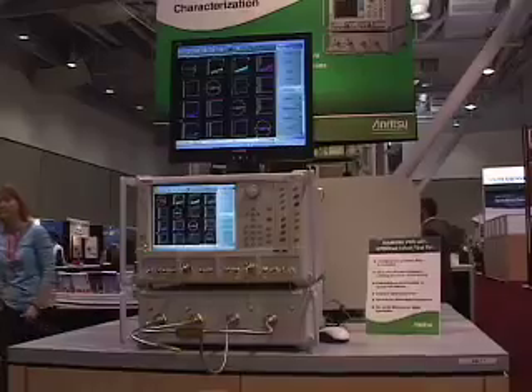Basically what we're doing is we're taking our switch technology and putting them into an external test set. The advantage of that is that you can add on the multi-port capabilities later on. So you can buy the 2-port now and add the 4-port later and not sacrifice on dynamic range. If we had it internally, we'd have to have many multiple switches where you lose dynamic range. Using this approach, we can optimize our dynamic range and measurement speed as well.